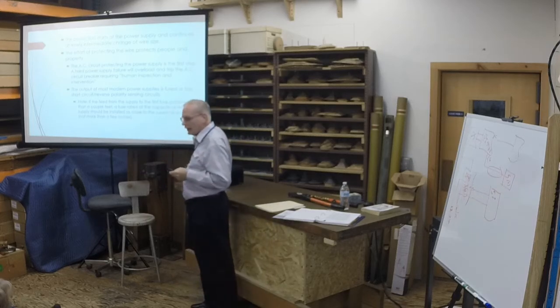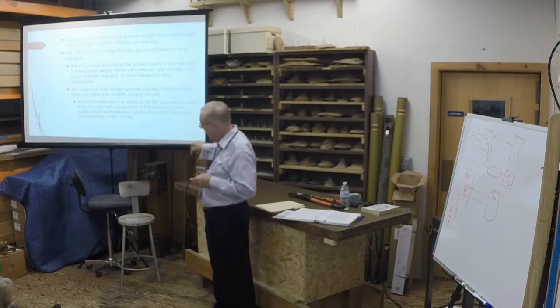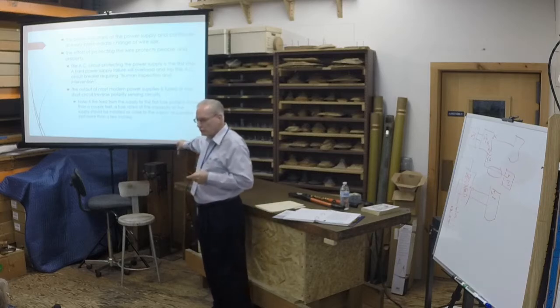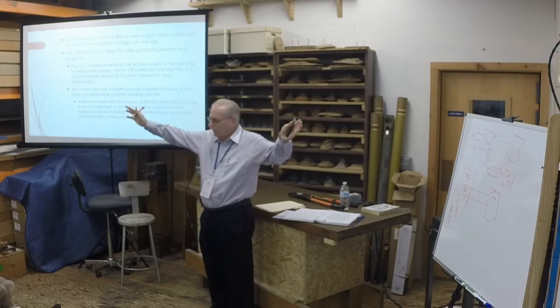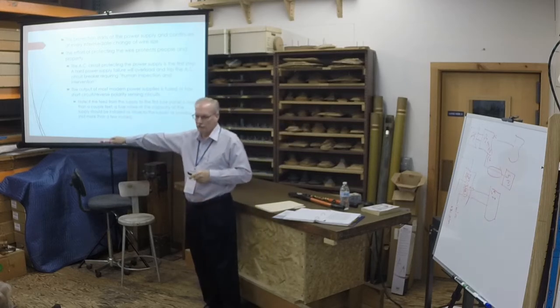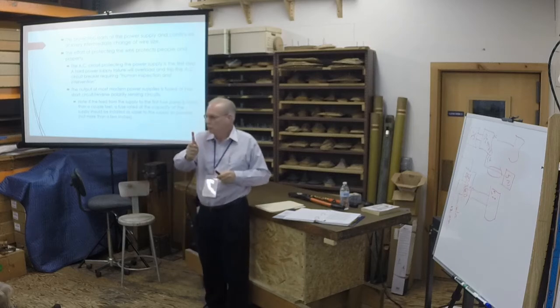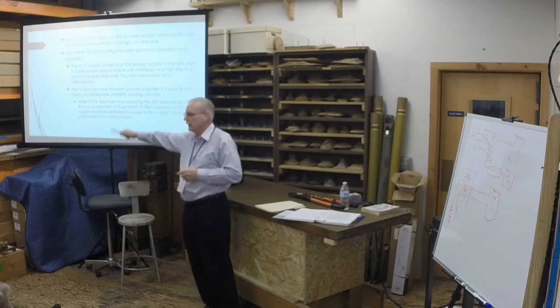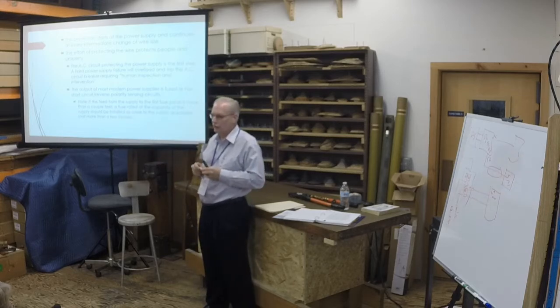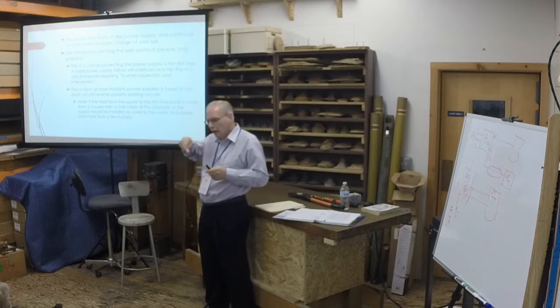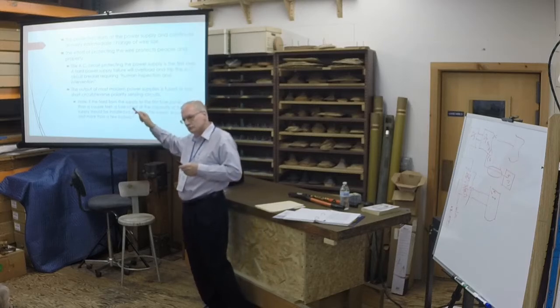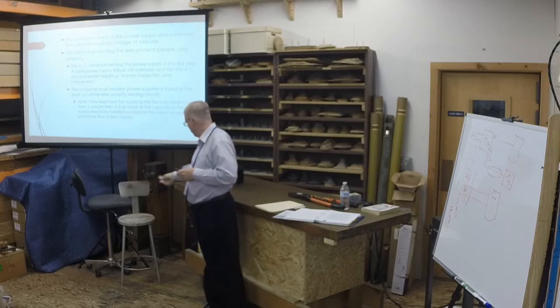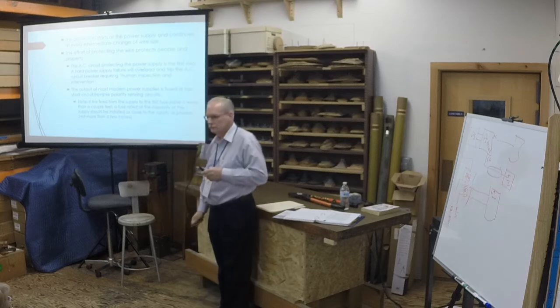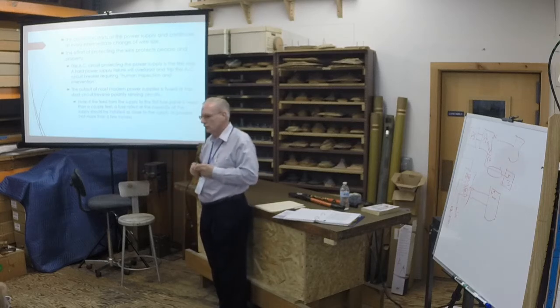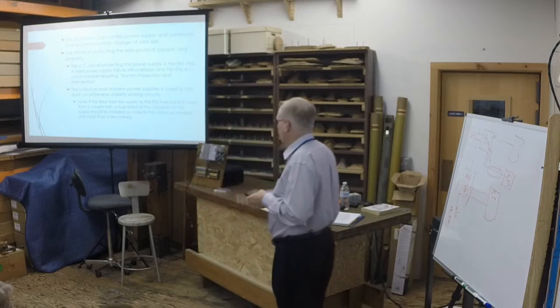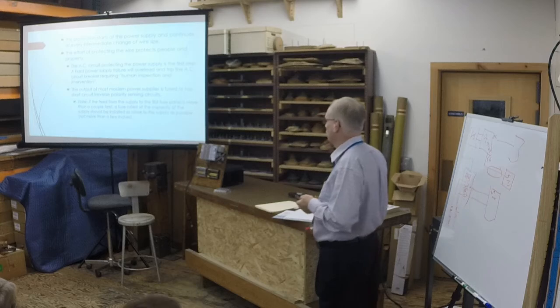But if you start getting further away from here, you gotta fuse that wire. You don't have a choice but to fuse that wire. If you got a bank of power supplies and your distribution's 10 feet away and you've sized your wire appropriately, you need to fuse where that starts making its trip. If you've paralleled a bunch of power supplies, okay, you can parallel the power supplies, but as you start making that trip to wherever you're going, if it's more than a foot or two, you gotta fuse it. Protect it, breaker it, however you want to do it. And I state that, get more than a couple feet, fuse it.